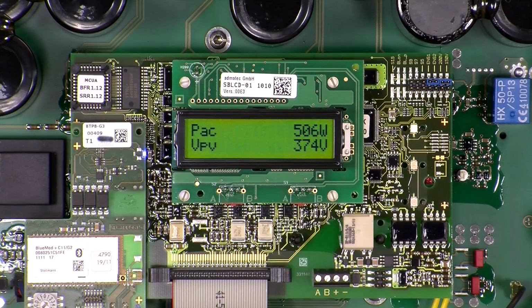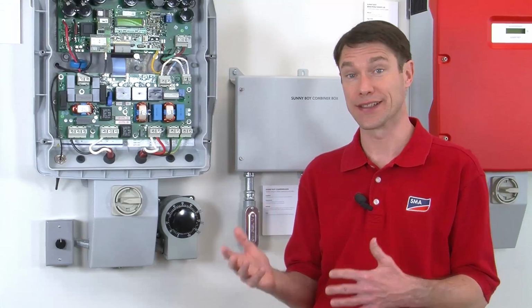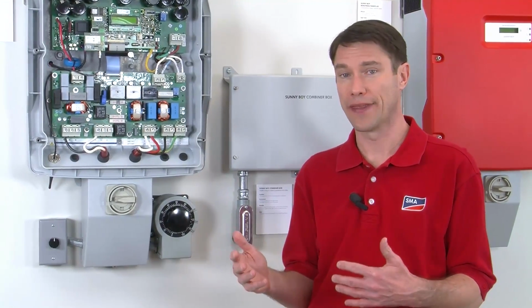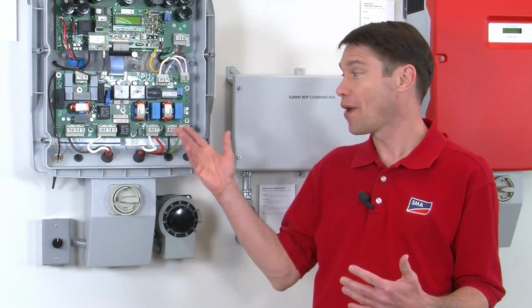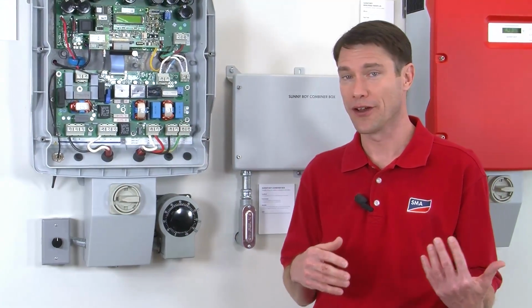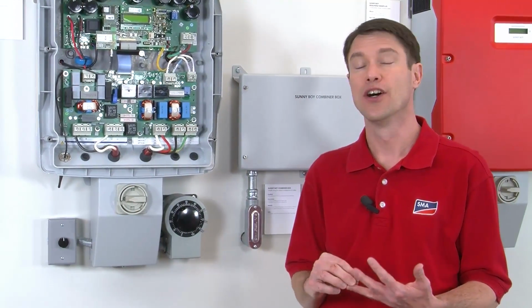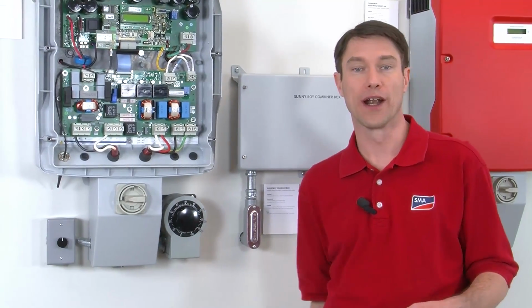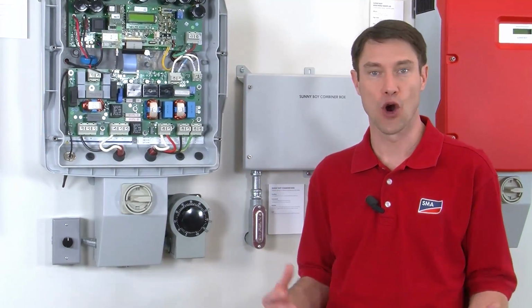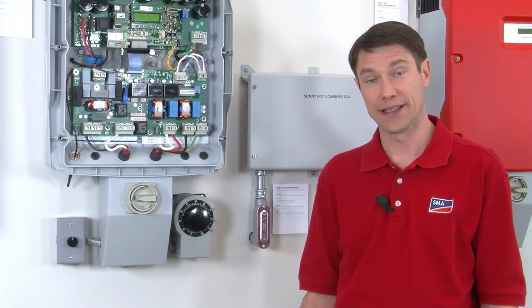And on the inverter, the display will cycle through several screens, so when you get the disturbance FAC, you'll also get a screen that shows what frequency on the AC side the inverter is actually seeing. So if you see 0 Hertz on that, you should be led to go back between the inverter and the utility panel to search for an open AC disconnect or an open breaker and find out where that missing connection, or the open connection, is. So that's an easy fix.